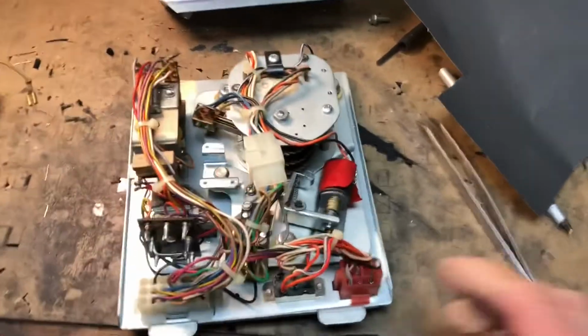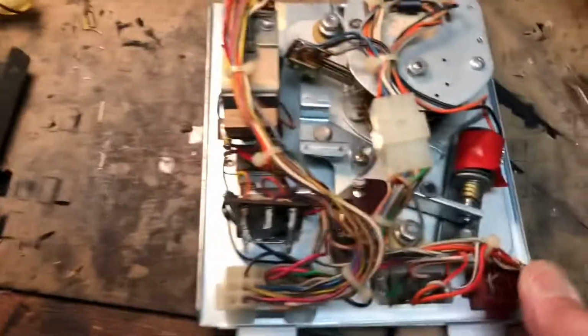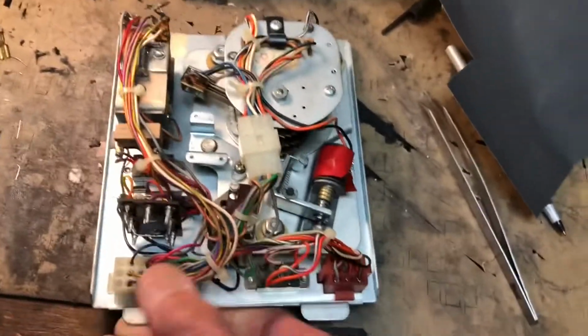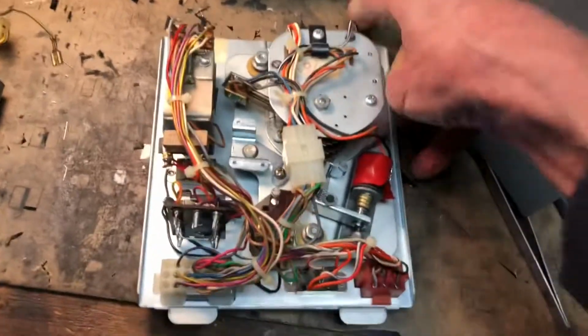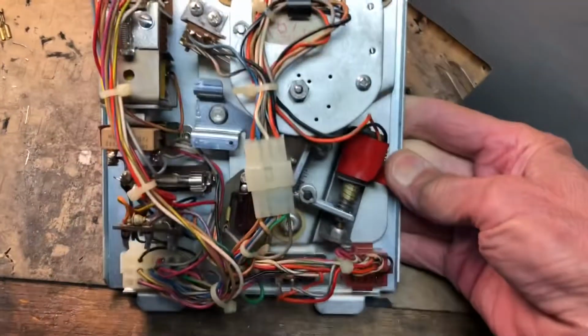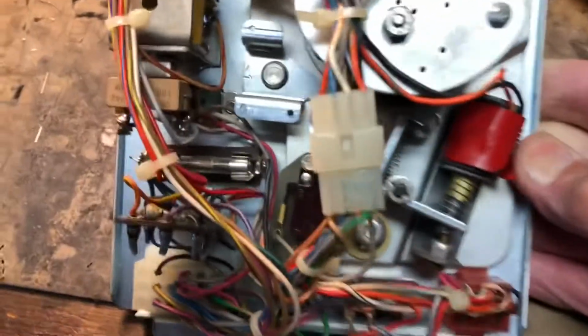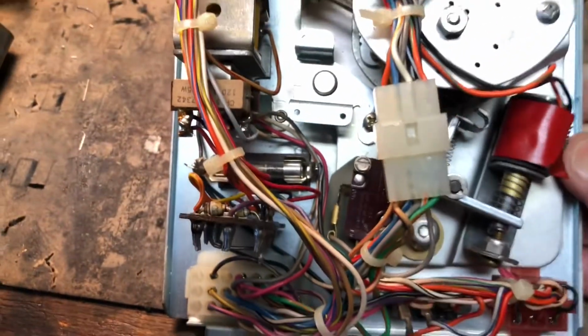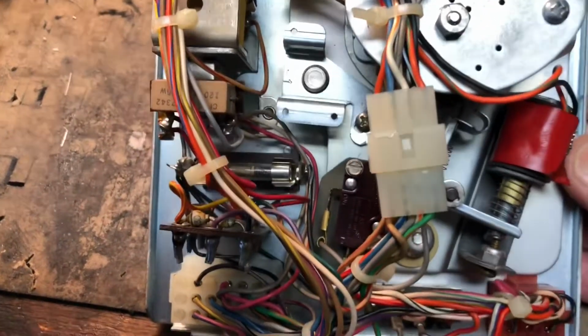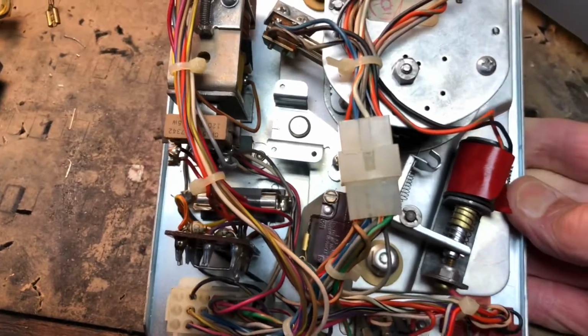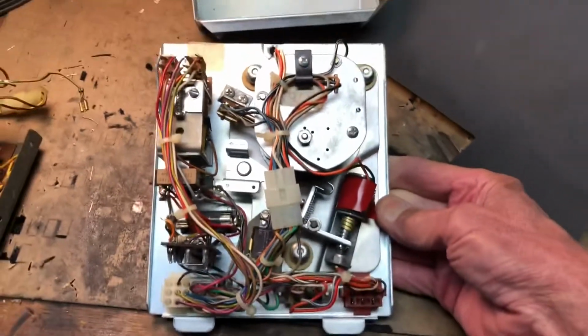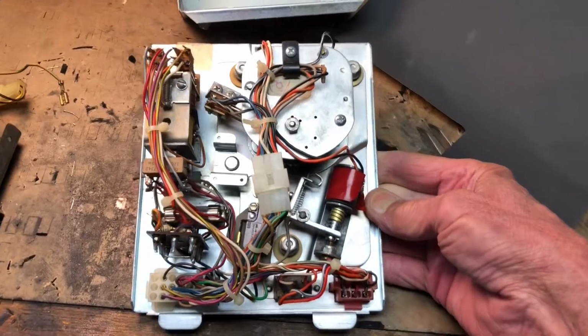It doesn't matter. Now, also, there's a 1/4. We're going to start to talk about fuses now, and obviously, if you're in here, there's a 1/4 amp slow blow fuse right there. Be sure that's not blown, and if it is blown, then you better look at the contacts and check some components. But this has normally been fairly trouble-free.